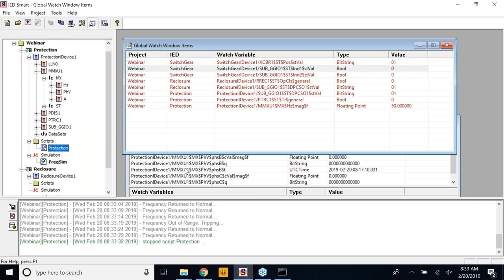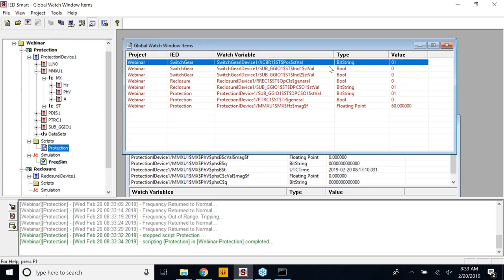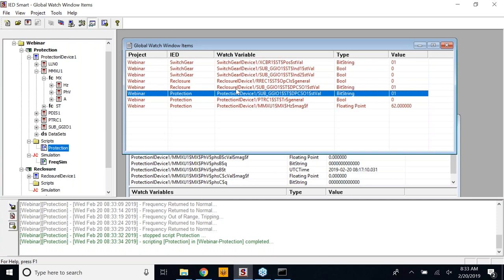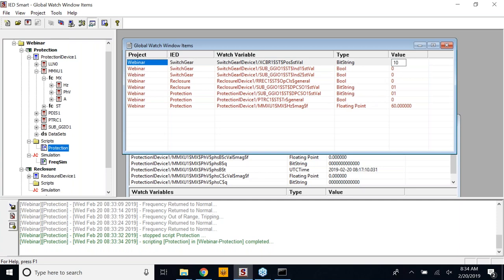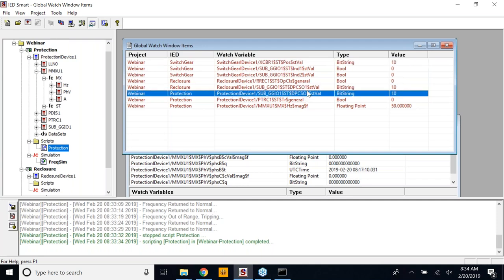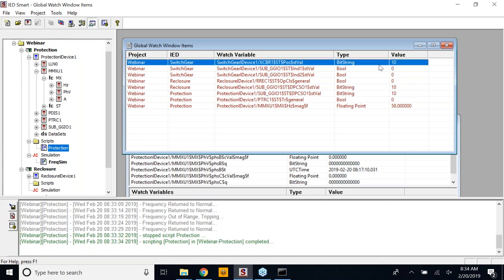What we were seeing was a trip signal going out to the switchgear. If the breaker position changes, let us see how the other devices respond. We are expecting to see that these values reflect the switchgear status because these values are subscribed in these devices. So let us make the change manually. You could see that these two signals were changed immediately as I changed the circuit breaker position because it is actually subscribed in these other IEDs. So we can see the same information from the client perspective.